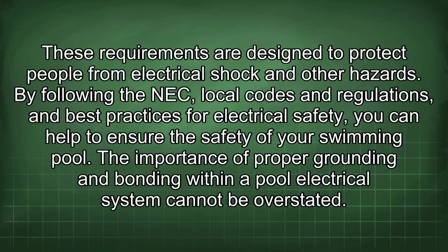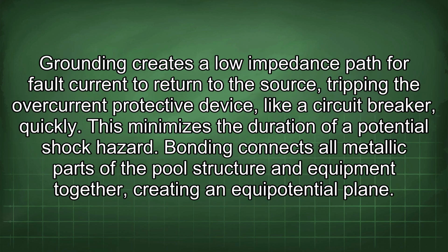The importance of proper grounding and bonding within a pool electrical system cannot be overstated. Grounding creates a low impedance path for fault current to return to the source, tripping the overcurrent protective device, like a circuit breaker, quickly. This minimizes the duration of a potential shock hazard.